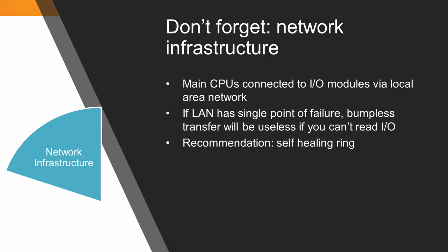As I commented earlier, we talked a little bit about the network, and in that architecture or topology that I displayed, we showed a ring that basically went between the primary, secondary, and all of the remote I/O modules. Typically what you want to do when you design a network is provide the capability that in the event of a failure in any of those segments of the network, the network will still continue to operate. So typically we'll see the use of what we call a self-healing ring. And that technology has been around for many years. There are many manufacturers who have created their own version of it using the rapid spanning tree protocol. But again, if you're going to go to the expense or the investment of designing a control system, you need to make sure that you pay attention to all the components, and the network is certainly one of those.